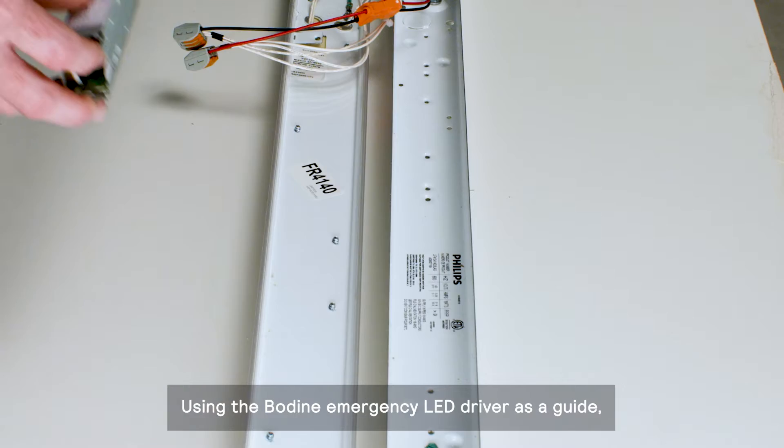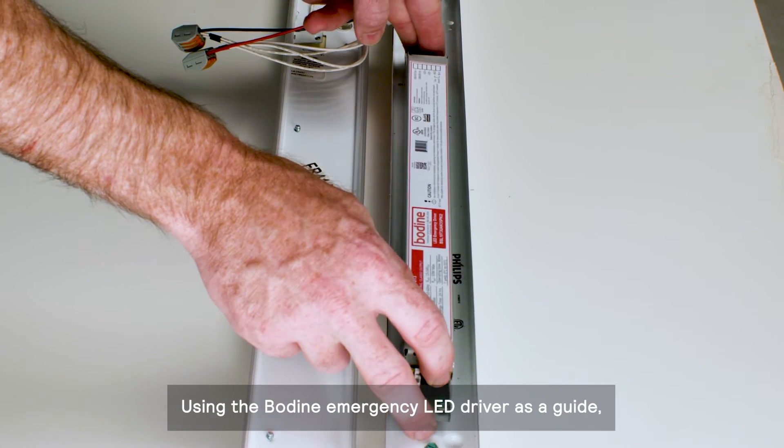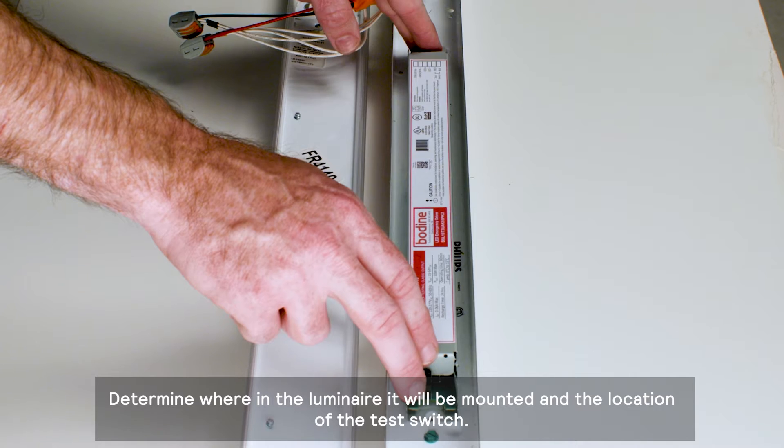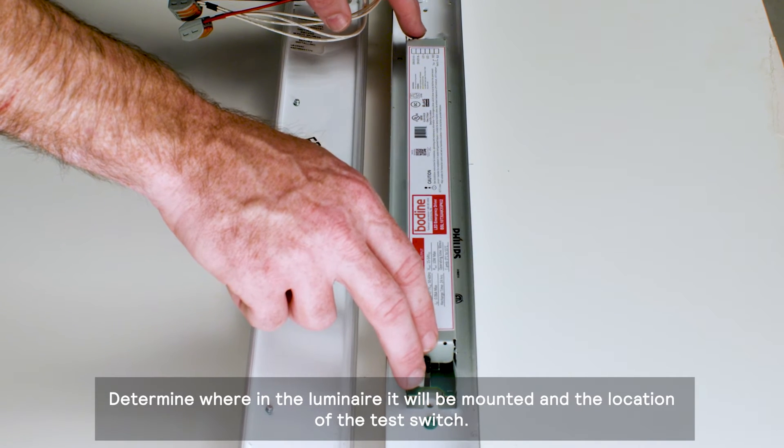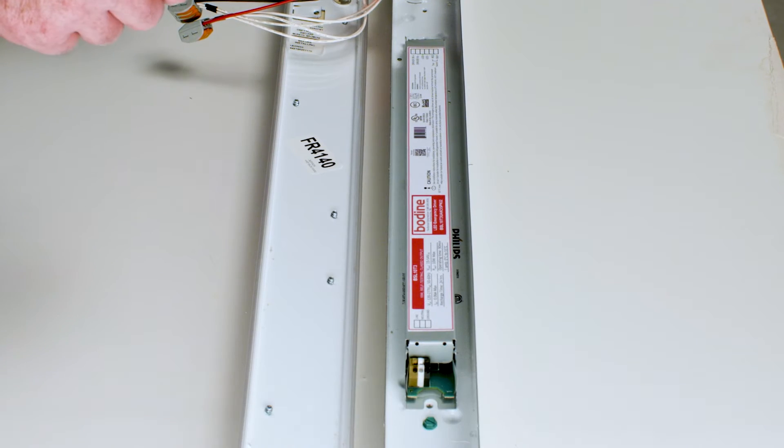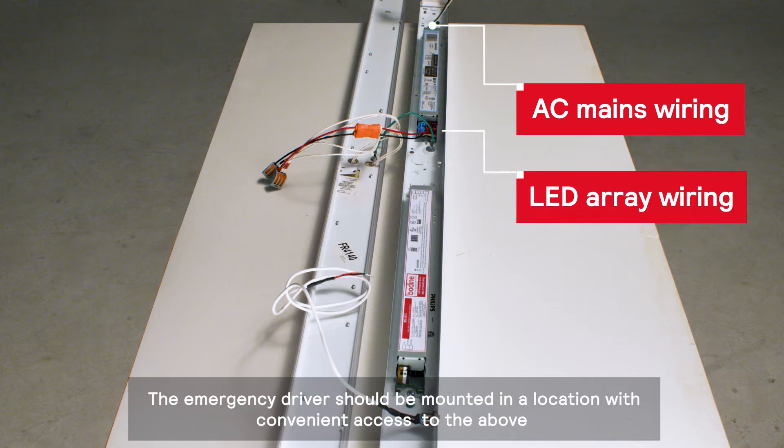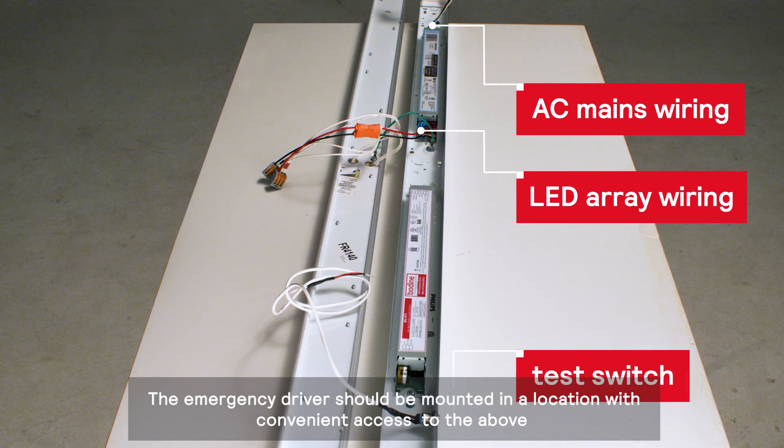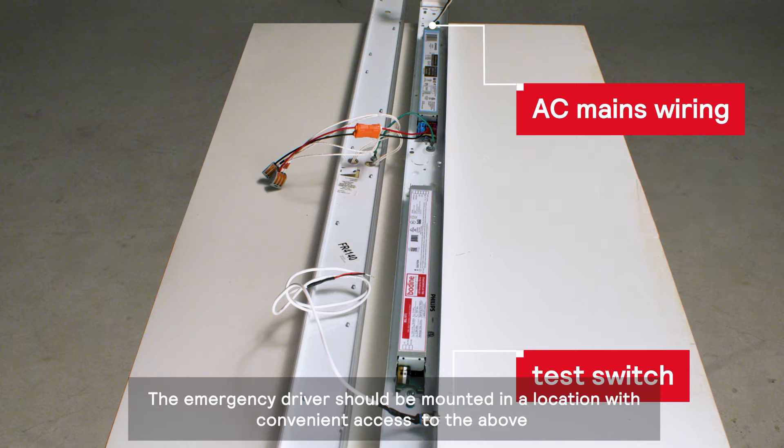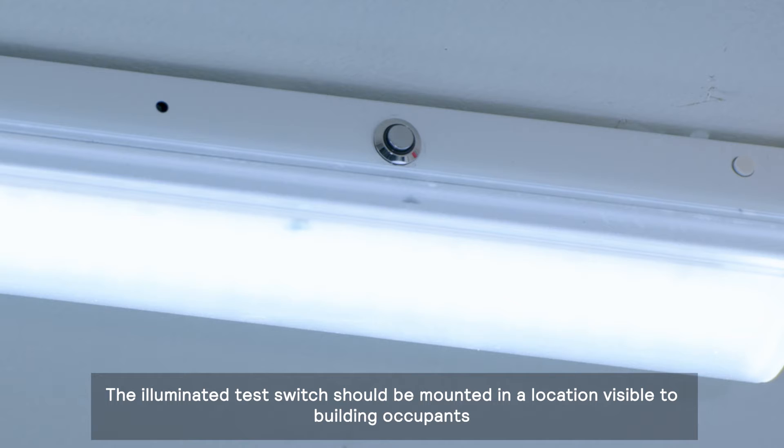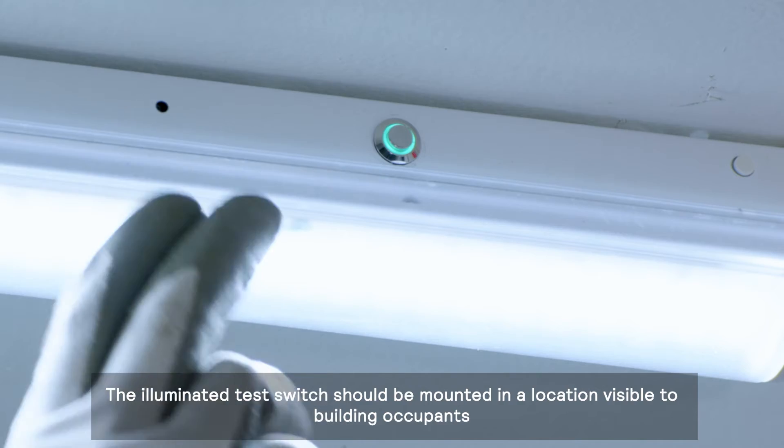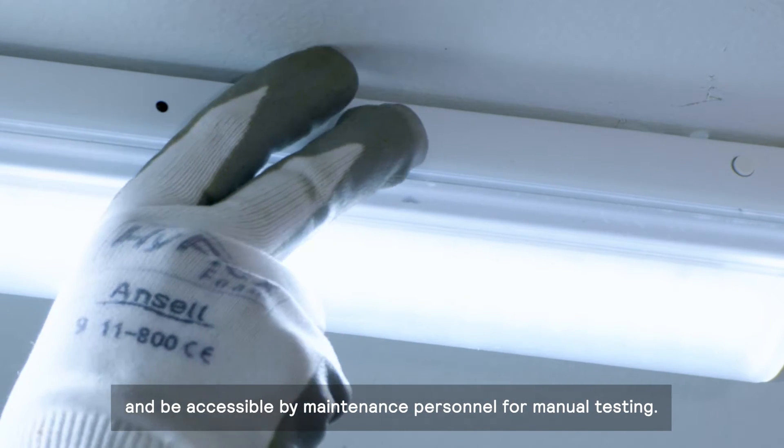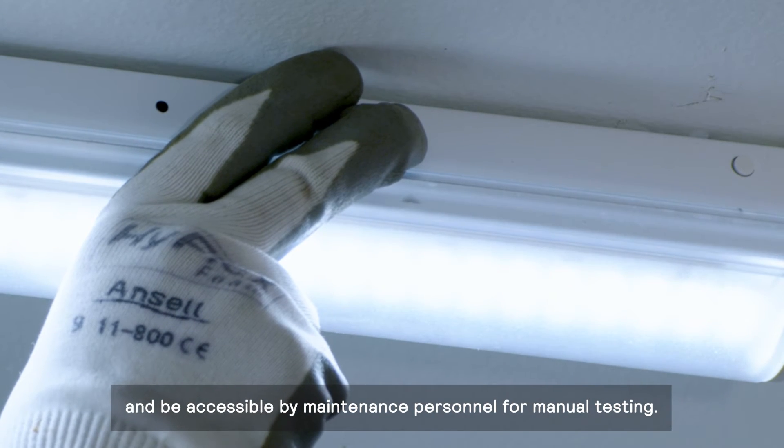Using the Bodine emergency LED driver as a guide, determine where in the luminaire it will be mounted and the location of the test switch. The emergency driver should be mounted in a location with convenient access to the LED array and AC mains wiring and the final location of the test switch. The illuminated test switch should be mounted in a location visible to building occupants and be accessible by maintenance personnel for manual testing.